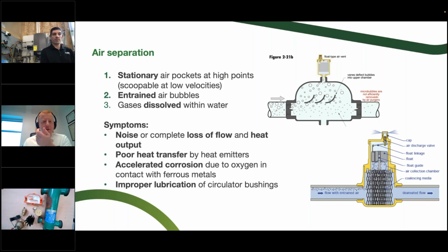And personally, Bob, I think that those are really great for the air management systems. When they were the top, instead of having an air vent on it, it was connected to a compression tank. So if any air got out in the system, it would collect back at that air scoop and then take it back up to that compression tank. After that, like you said, without the coalescing media, without the ability to take out the microbubbles, you're not really doing that system any justice.